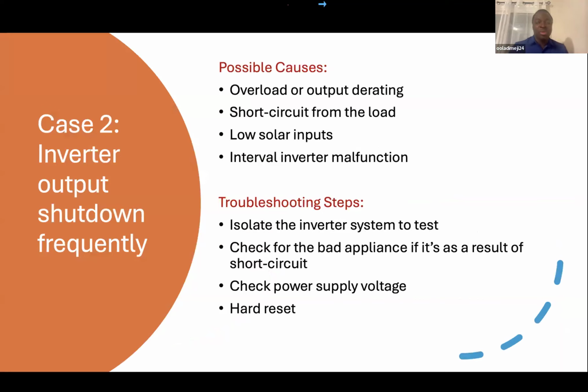Case number 2, inverter output shutting down frequently. Like I discussed, sometimes it's caused by overload or output derating. On a Genex inverter, you have error 10, which is output derating, when your input voltage is much lower than the acceptable input voltage. Because it's passing the same to the output, that's what you're going to get at the output too, so it gives that error warning. Other causes are short circuit, low solar output, or internal inverter malfunction.